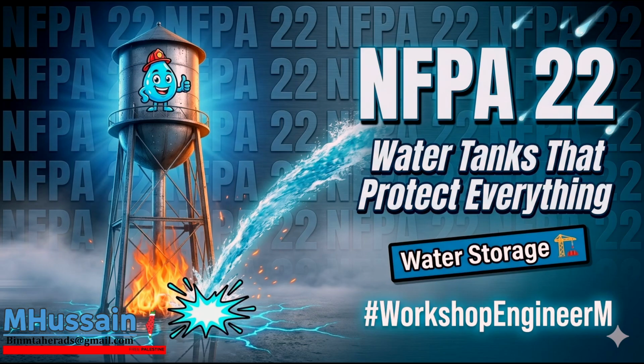And if your calculations show the fill line is too small to achieve that 8-hour window, the design is legally non-compliant. Period. Furthermore, if the tank is not at its sufficient calculated capacity at any point, the standard triggers the impairment procedures outlined in NFPA 25. Which means what, practically? You essentially have to declare the fire protection system compromised. That can force a facility to halt operations, institute continuous fire watches, and notify insurance carriers. The 8-hour rule is a massive operational constraint. So we've established the mechanics of standing, unpressurized water.